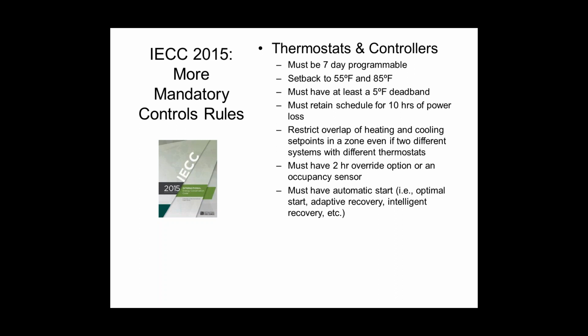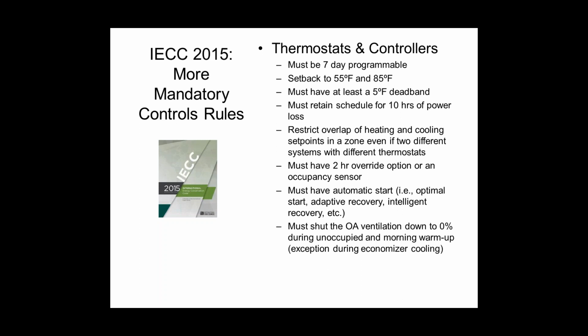Lots of thermostats are available with this technology. It's been around for 20-plus years, but you have to make sure you buy or specify one that does it and then enable the feature as well. It's typically defaulted off. And like I mentioned in the economizer discussion, something has to shut the outside air damper down in the middle of the night, during an unoccupied period when nobody's there. Typically, that's going to have to be the thermostat or the DDC controller, because there's nobody else that can shut it down automatically.